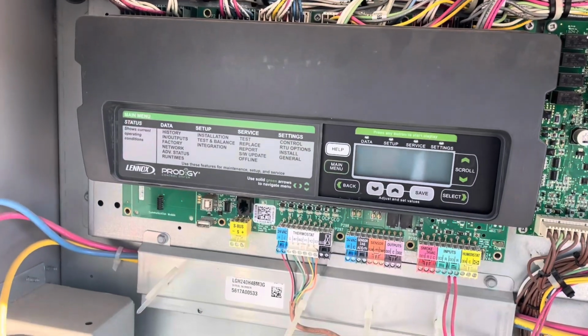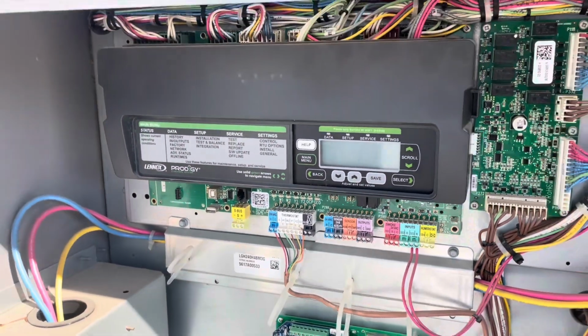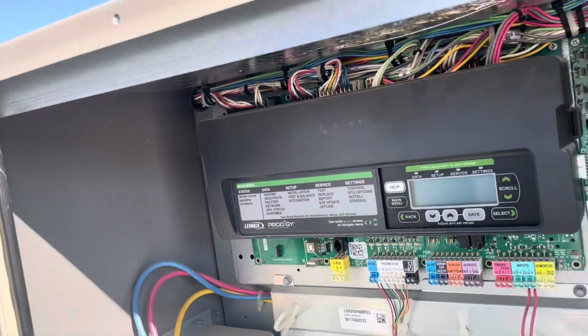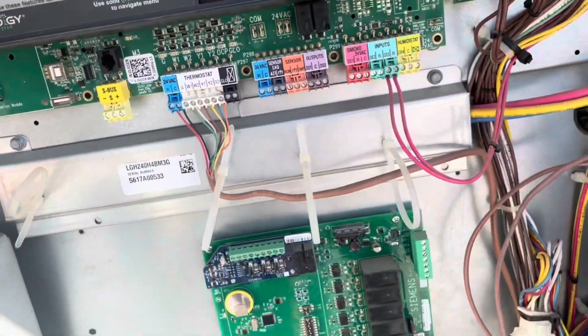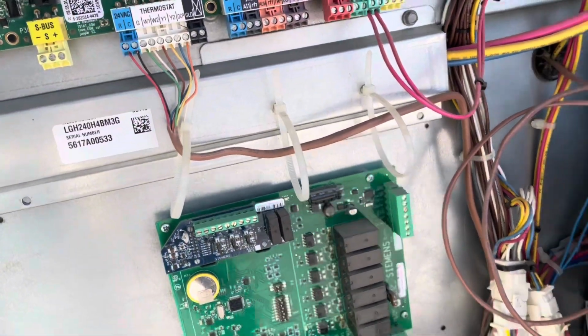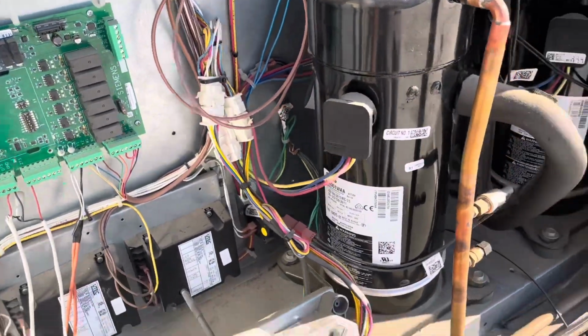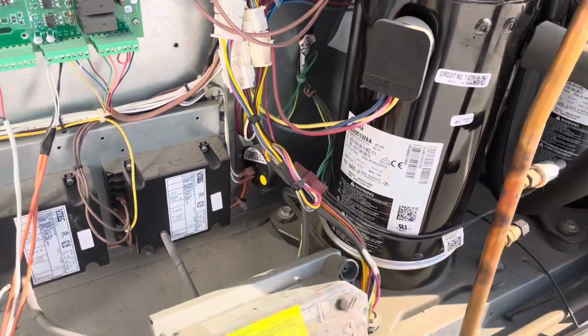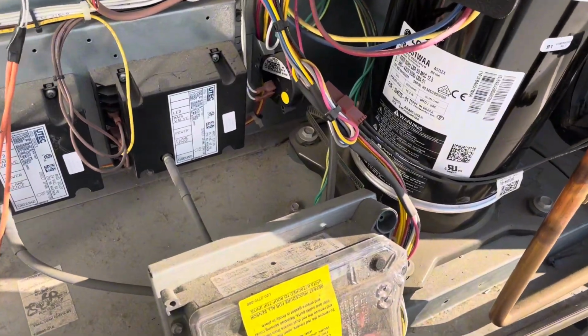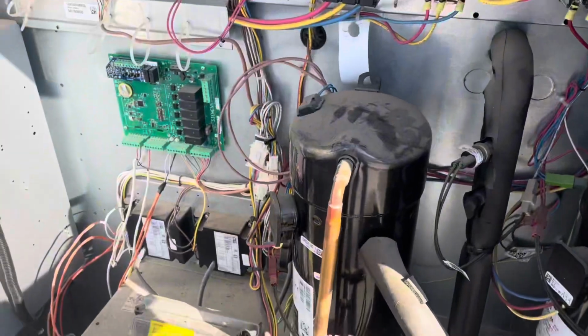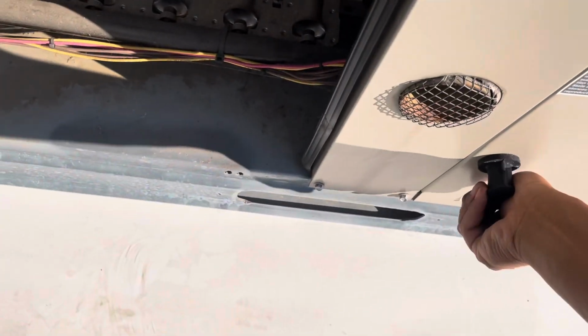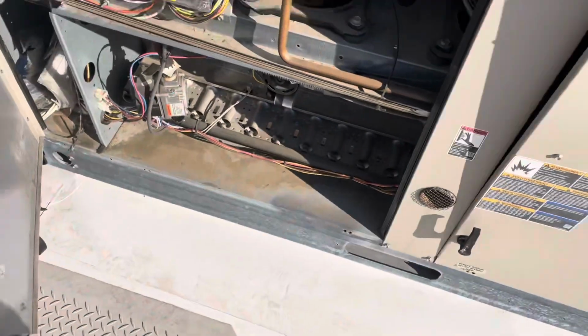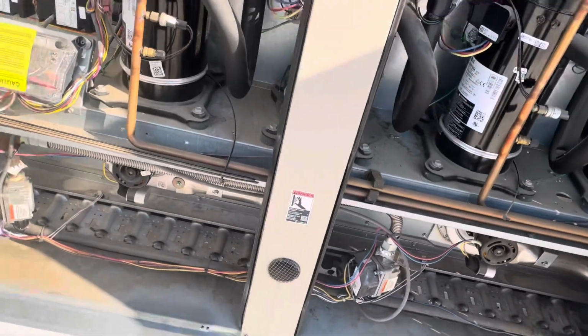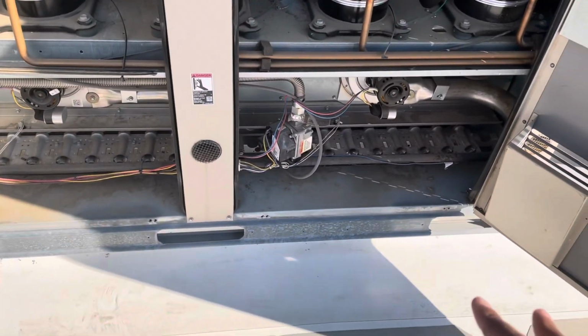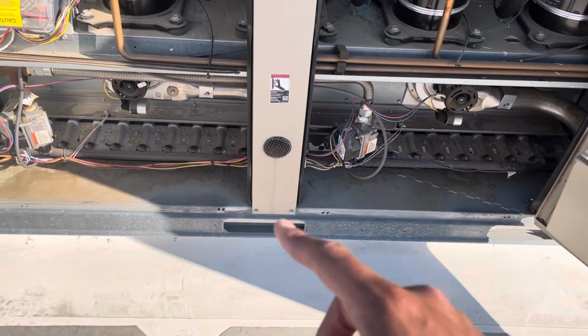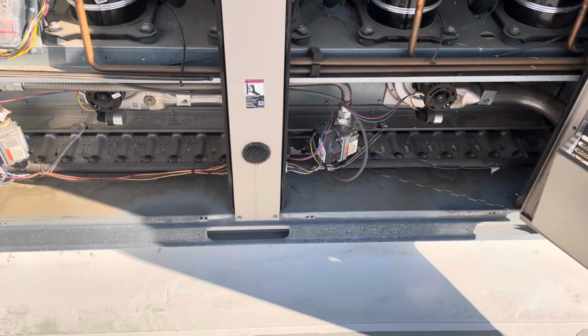Alright, so there's the Lennox Prodigy control, the newer Lennox Prodigy control. So I'm going to take you through the process. It is still actually pretty warm today, so I'm not going to leave the unit in heat for too long. But again, I want to show you the process and what to check and what to look out for and things like that. So I'm going to open this up. All right. So the heating section on these models is at the bottom. We have 2 heat exchangers, 2 inducer motors, 2 gas valves, 2 manifolds. So we have 2 heating circuits.